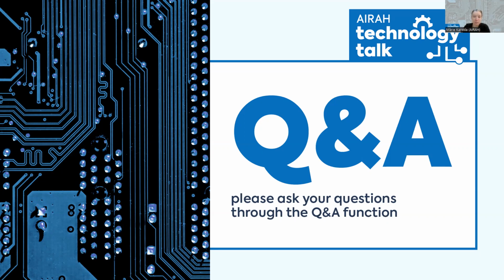Next question we have there is, what is the main difference between BACnet and Modbus? Yeah, great question again. And how much time do we have? Because they're two totally different protocols, really. BACnet itself is a protocol developed for HVAC systems by ASHRAE in the US, and it is a very common integration protocol. The biggest difference that I can say is that there's a lot of automated stuff in BACnet where you can auto-discover devices, you can connect and get things running pretty quickly.